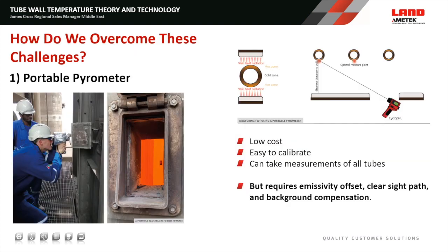So how do we overcome these challenges? The first is through portable pyrometry. This is a very common method used in the syngas industry — low cost, easy to calibrate in a black body furnace, and it can measure all tubes through peepholes. However, it does require an emissivity offset, a clear sight path, and background correction.